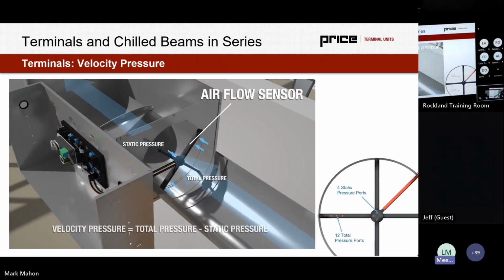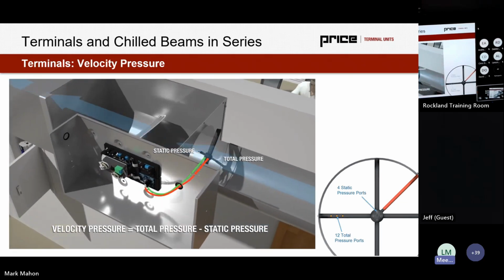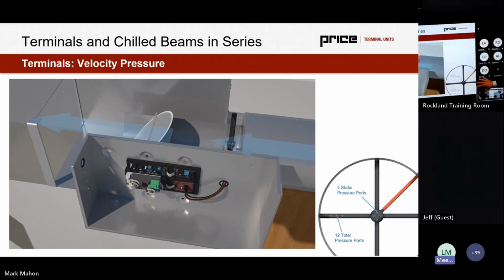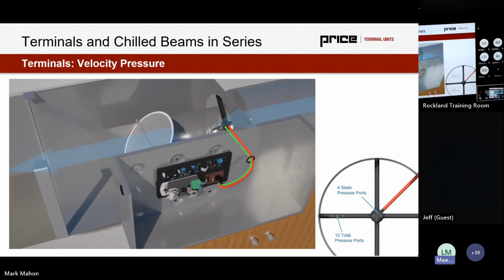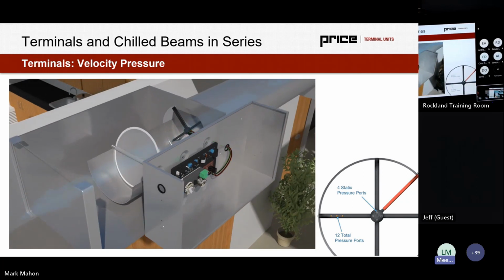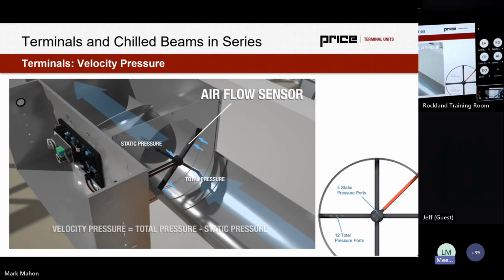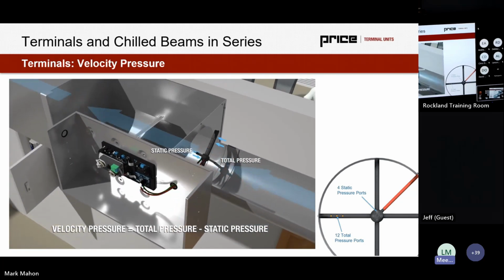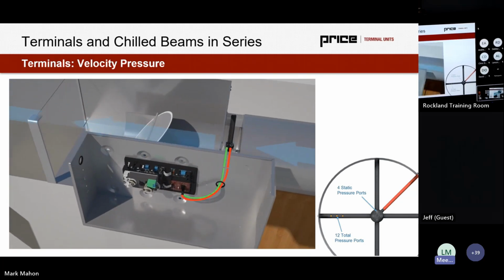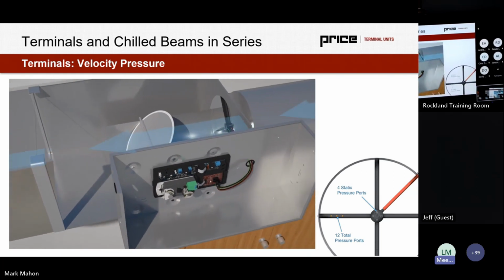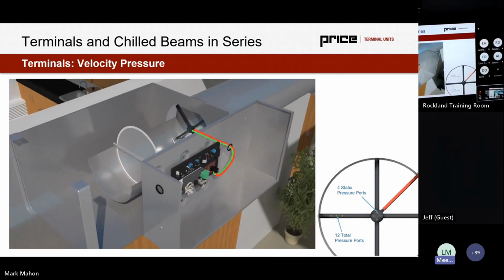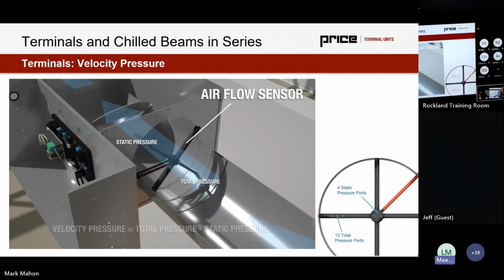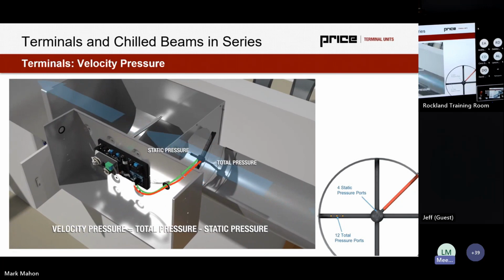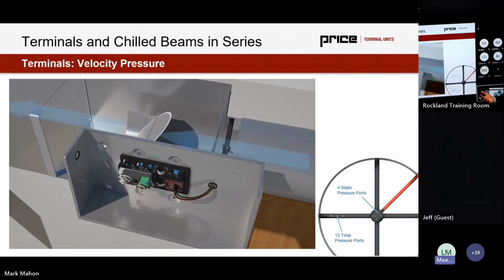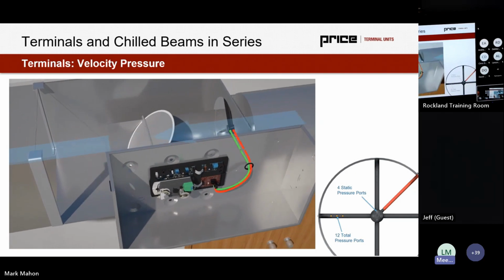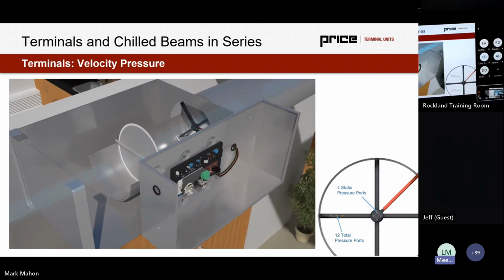Now, when we look at velocity pressure, that's what we're using to actually measure and control airflow. And so our crossflow sensor, the one from Price, is called the SP300 crossflow sensor. Very critically, a crossflow sensor adds a lot of value to projects because it's going to allow us to have a kind of uniform duct sampling of pressure throughout the duct, which means if we have flex duct or if we have an elbow, we're going to have less weight and influence from localized velocity, so better airflow measurement and control. And what this sensor is actually doing is it's measuring total pressure, or the summation of velocity pressure and static pressure.